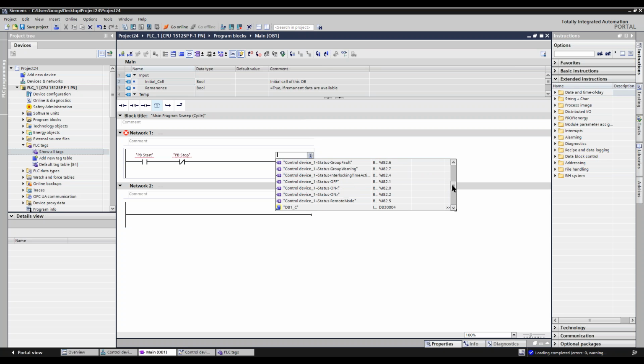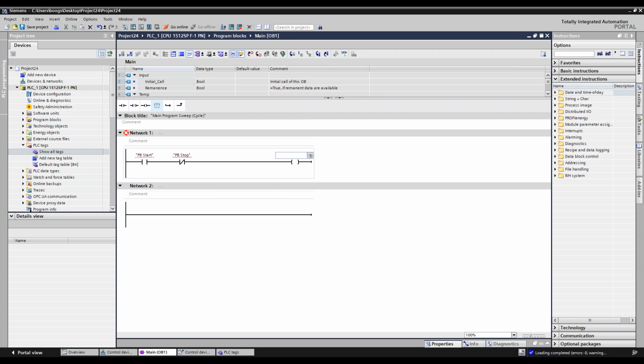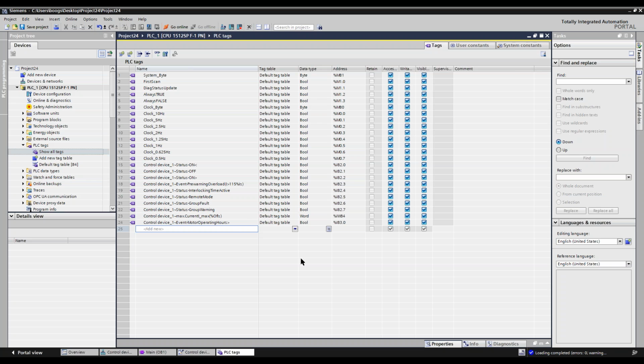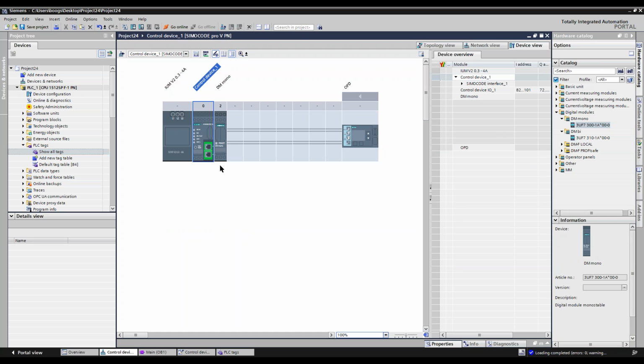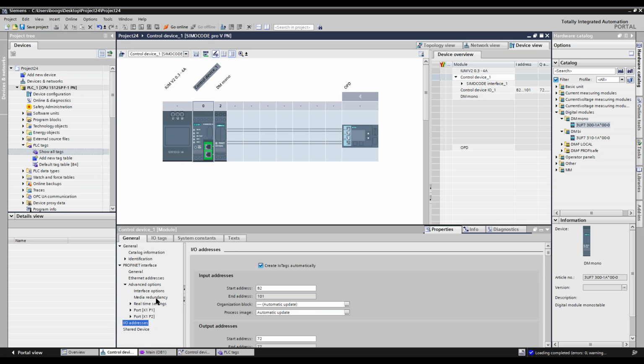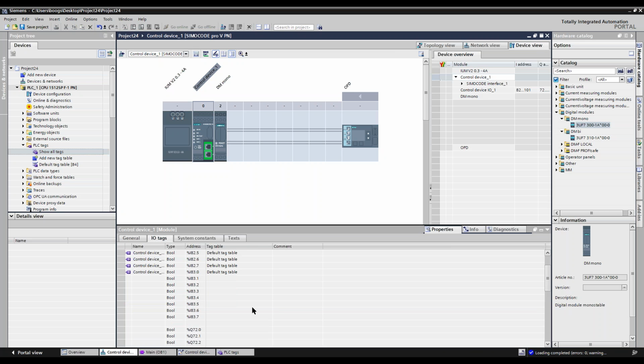I apologize. Let me click on here. Oh, I need to give it a name, so I'm going to say motor 1. All right, and those tags are in there for that. And then I'm going to go grab the PLC tag. Let's show them all. Again, I've done the inputs, but it didn't do the outputs. So where I go to do the outputs, I double click here and go to IO tags. There's the IO tags for the inputs that have already been created. Now I need to go here, and I know that this first tag is motor forward, and the next tag is motor reverse.